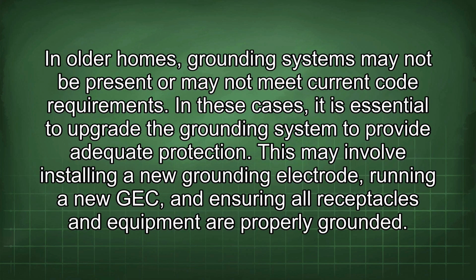In older homes, grounding systems may not be present or may not meet current code requirements. In these cases, it is essential to upgrade the grounding system to provide adequate protection. This may involve installing a new grounding electrode, running a new GEC, and ensuring all receptacles and equipment are properly grounded.